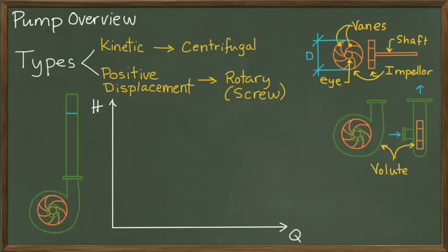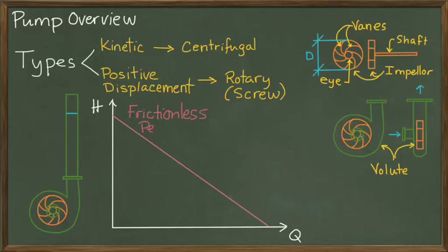Another way to look at this is in terms of what we call the pump performance curves. If we plot the relationship between discharge and head, one can see that as discharge increases, head decreases, or alternatively, as head increases, discharge decreases. For a frictionless system, that's a perfectly straight-line relationship between discharge and head.